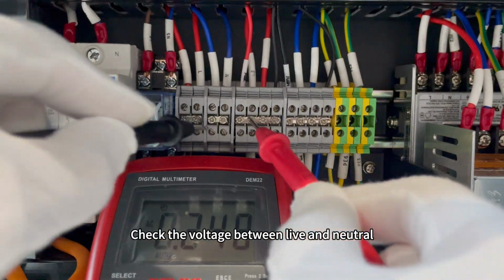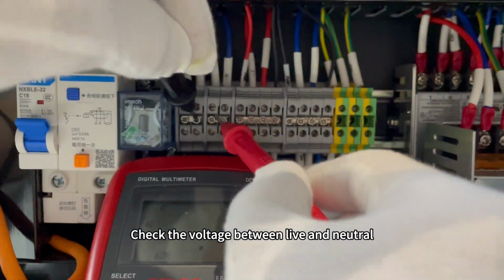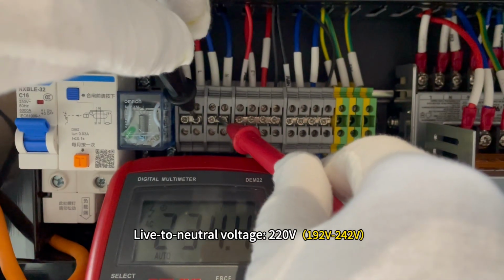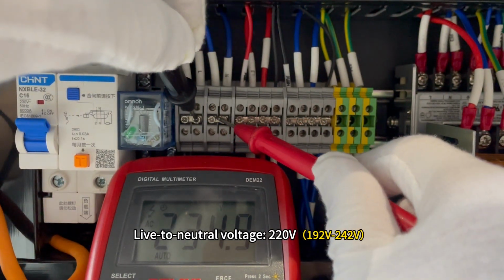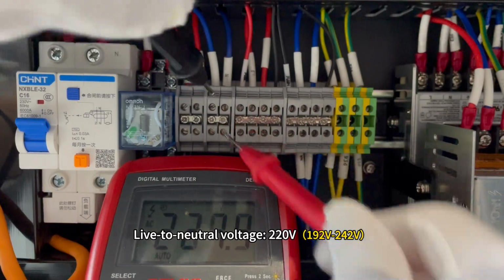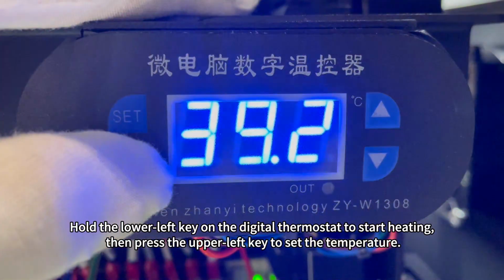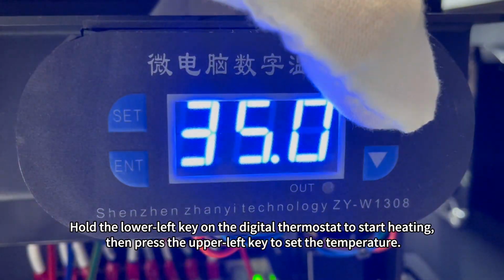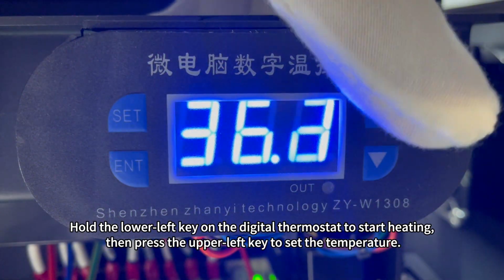Voltage measurement. Check the voltage between live and neutral. Live to neutral voltage, 220 volts. Hold the lower left key on the digital thermostat to start heating, then press the upper left key to set the temperature.